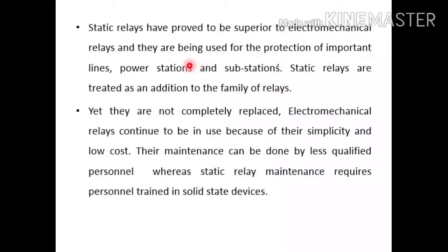They are more superior to electromechanical relays, and they are being used for protection of important lines, power stations, and substations. Static relays are considered to be an addition to the family of relays. Yet they have not completely replaced the others. Electromechanical relays continue to be used because of their simplicity and low cost, and they have less maintenance and require a less qualified person, whereas the static relay requires personnel trained in solid state devices.